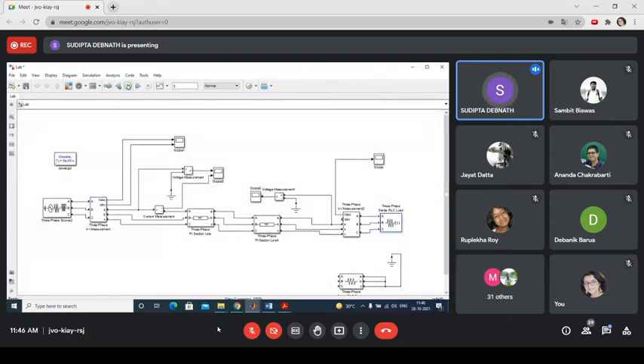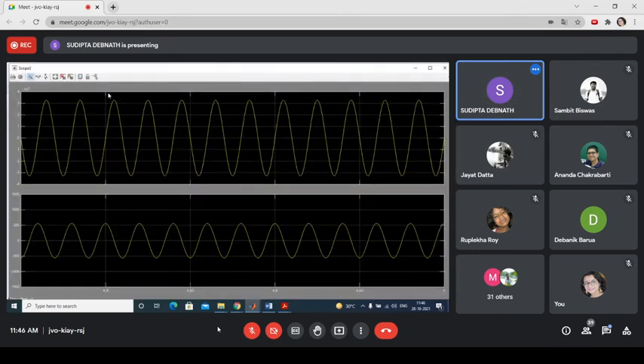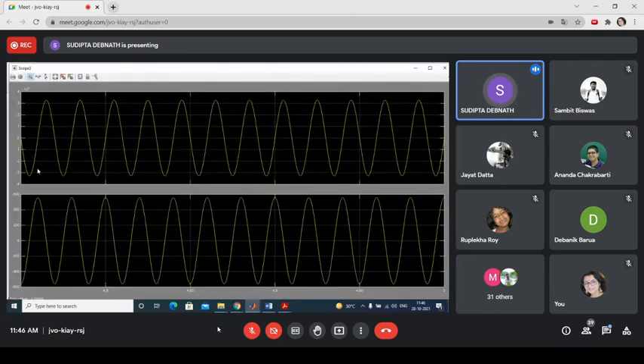You know, for a long transmission line under unloaded condition, the generated reactive power is much more, so the capacitive effect is much more. What happens when the capacitive effect is much more? It is almost - see, here it is starting at zero, and it is almost reaching its negative maximum value here. So there's almost a 90 degree phase shift.